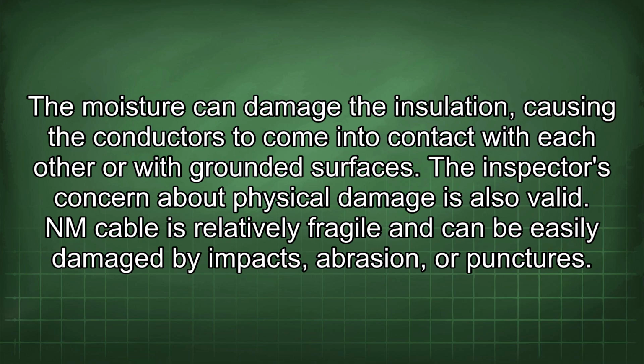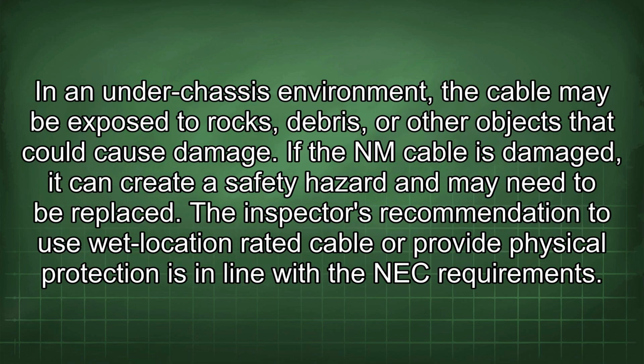The inspector's concern about physical damage is also valid. An NM cable is relatively fragile and can be easily damaged by impacts, abrasion, or punctures. In an under-chassis environment, the cable may be exposed to rocks, debris, or other objects that could cause damage. If the NM cable is damaged, it can create a safety hazard and may need to be replaced.